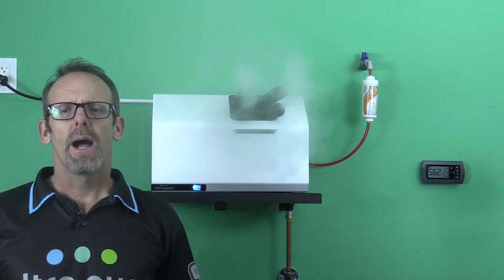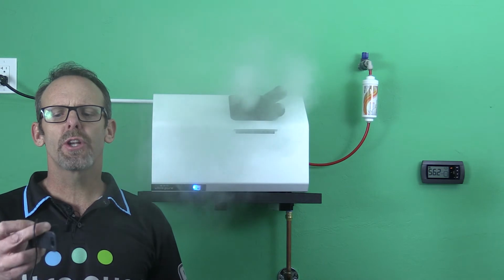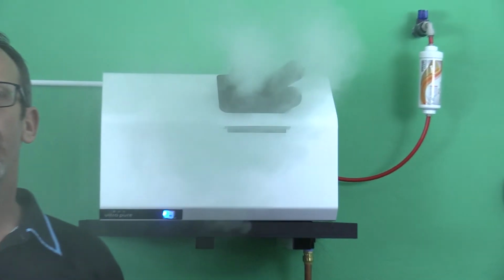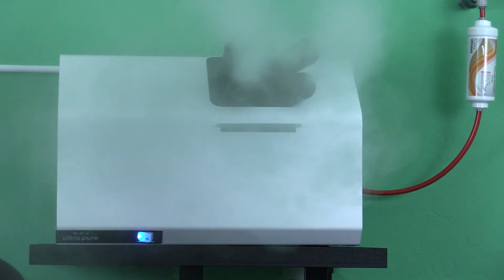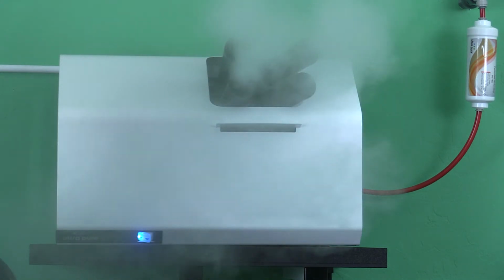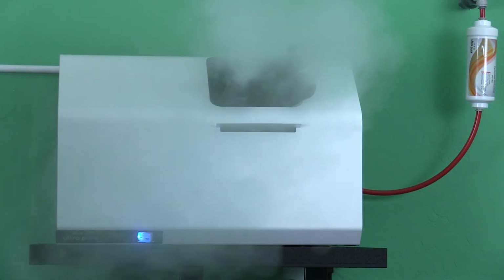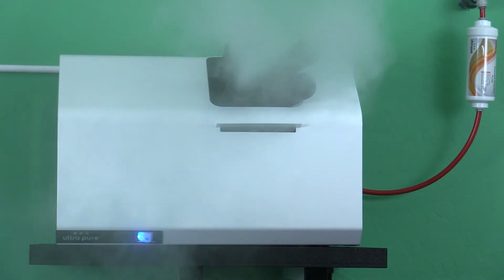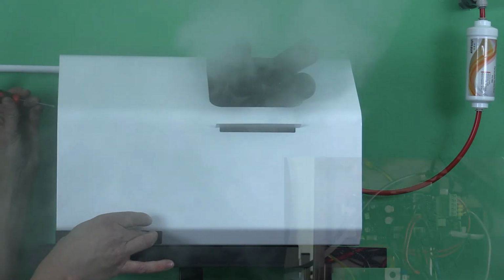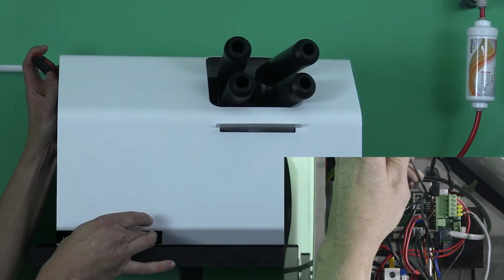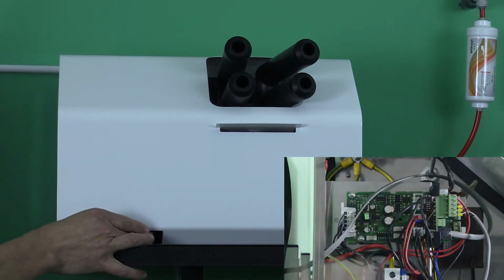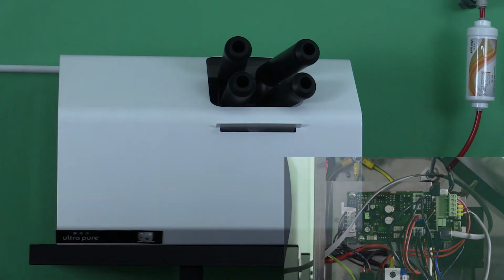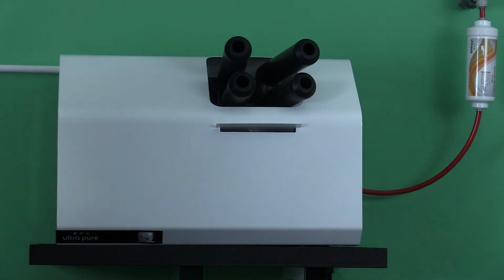Let's do that together. I'm going to go ahead and zoom in here now so you can start to see this humidifier, the way it's pulsating right now. We're within the hysteresis, and you can tell that they are pulsating and everything is fine, but if you want to limit that, this is the way to do it. We're going to turn off the humidifier at the switch and turn on dip switch number 8 with the small screwdriver. Turn the humidifier back on, and at that point, that's all you need to do.